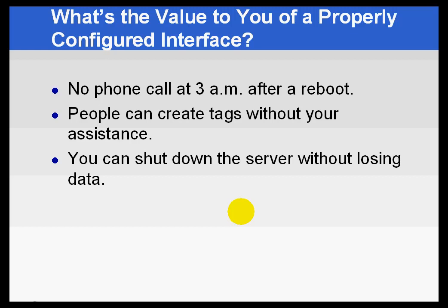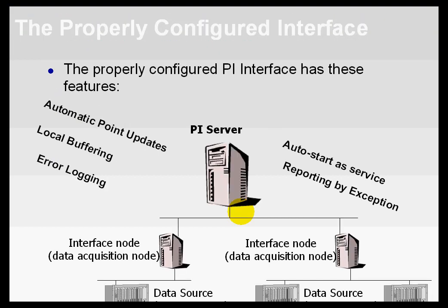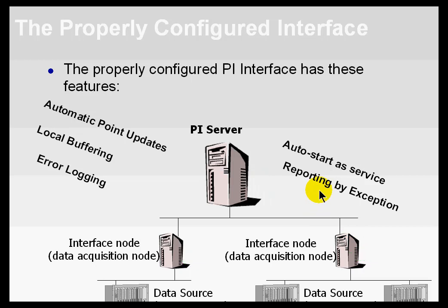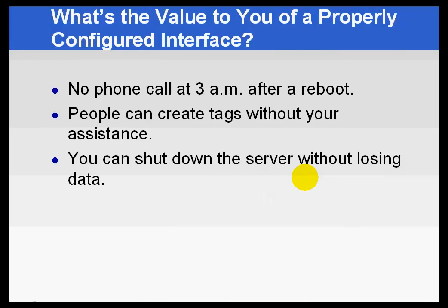If the PI Server is shut down for whatever reason, it will automatically buffer data locally — that's the shutdown or disconnect scenario. This means you can deliberately do a graceful shutdown of the server and these interface nodes will buffer data while that shutdown is occurring. When we first implemented that feature, it was a great boon to system managers because all of a sudden they didn't have to come in on nights and weekends to upgrade the PI Server. Previously, that would be the only time management would allow upgrades, because people were depending on the data and didn't want to lose it during an upgrade.